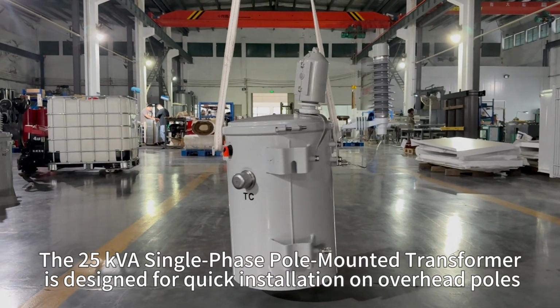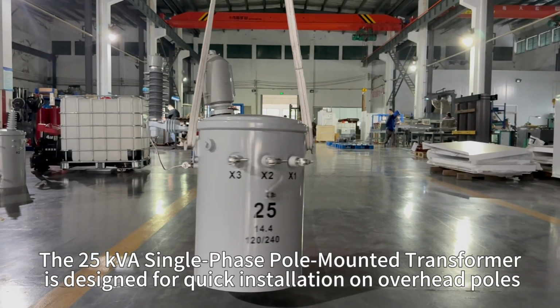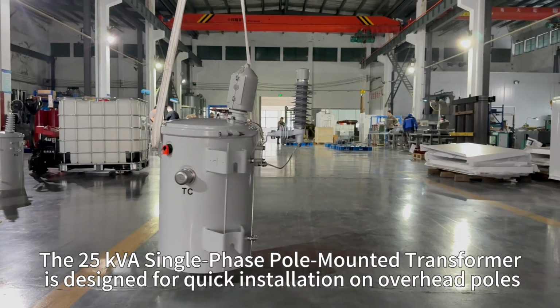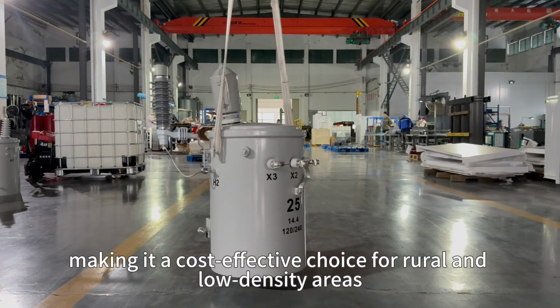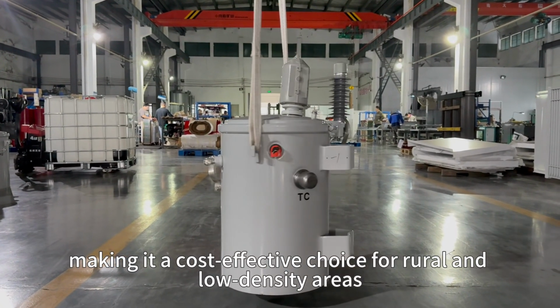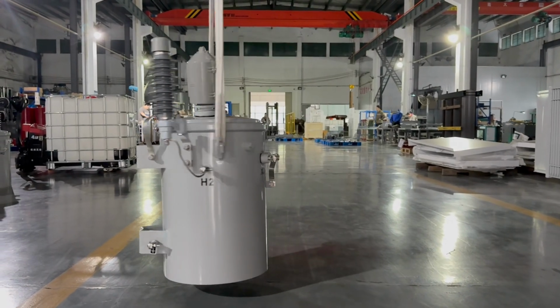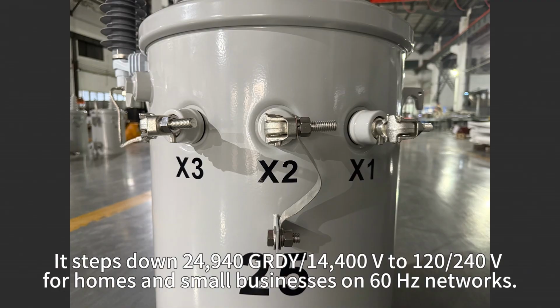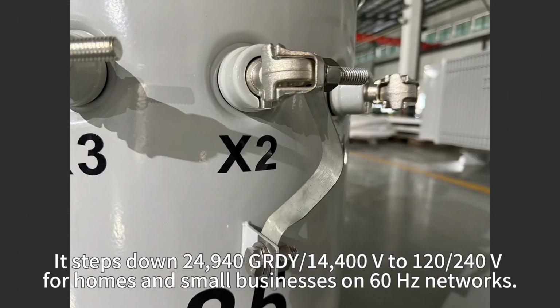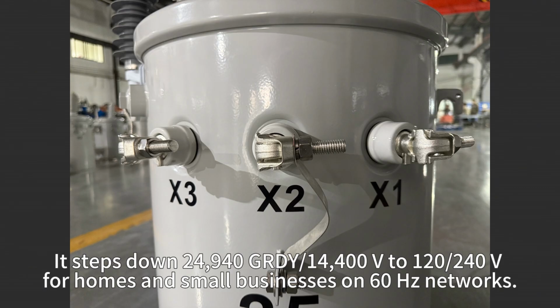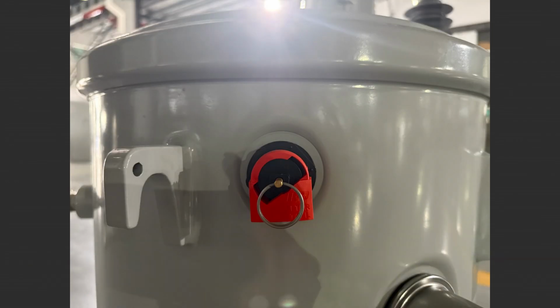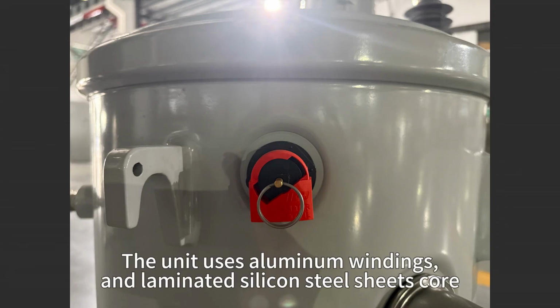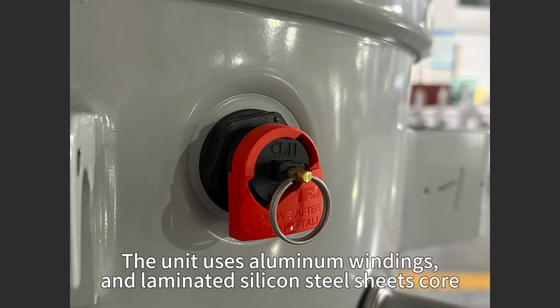This 25 kVA single-phase pole-mounted transformer is designed for quick installation on overhead poles, making it a cost-effective choice for rural and low-density areas. It steps down 24,940 GRDY/14,400V to 120/240V for homes and small businesses on 60 Hz networks. The unit uses aluminum windings and a laminated silicon steel sheet core.